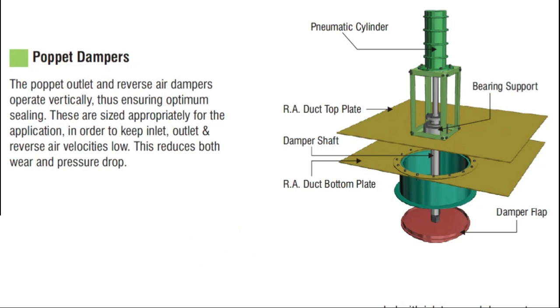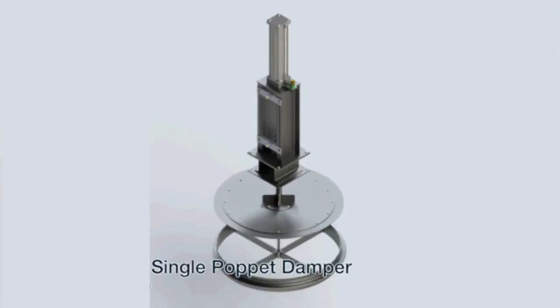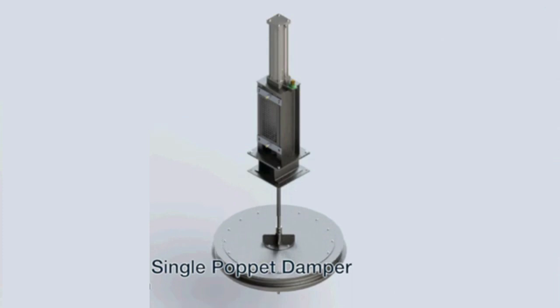Poppet dampers and reverse air dampers operate vertically, ensuring optimum sealing. They are sized appropriately for the application in order to keep inlet, outlet, and reverse air velocities low, which reduces both wear and pressure drop. The damper assembly includes a pneumatic cylinder, which operates by air pressure. While doing maintenance, you need to take care of these cylinders.